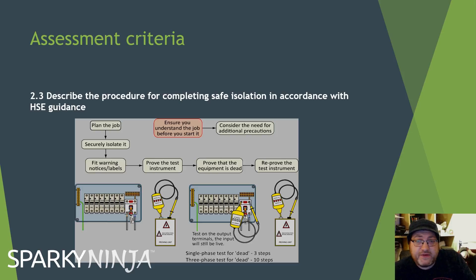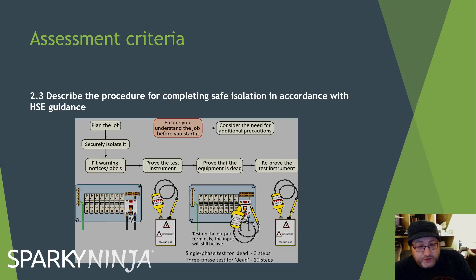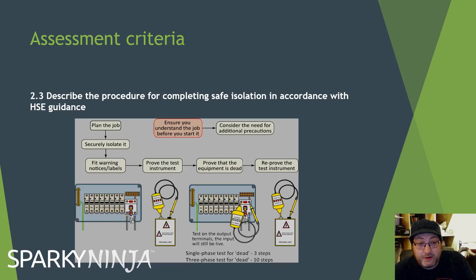The key thing is whether it's single phase or three phase. For single phase, you have three terminations: line to neutral, line to earth, neutral to earth. For three phase, you have ten: neutral to earth; line 1, 2, and 3 to neutral; line 1, 2, and 3 to earth; then line to line — line 1 to line 2, line 1 to line 3, and line 2 to line 3. There are ten in all — make sure you can jot them all down in a way that you can describe it well.